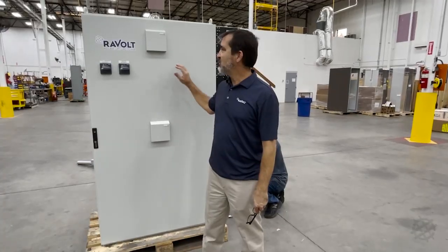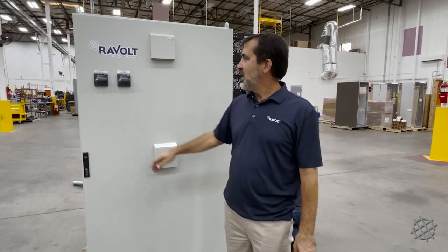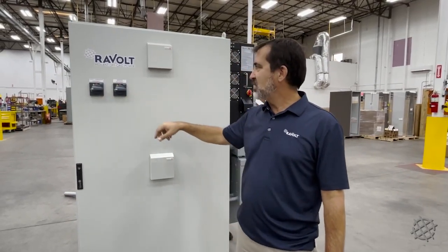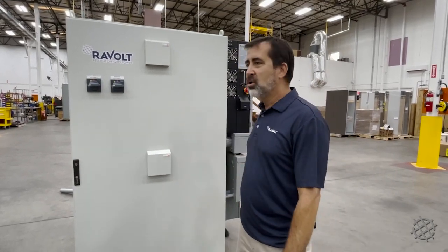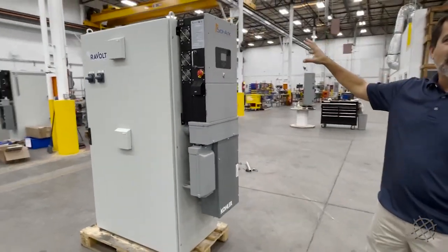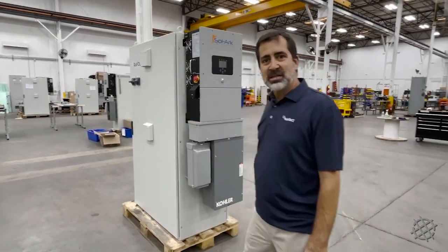We're standing right here in our manufacturing plant in Georgia looking at a Ravolt unit. This is our Level 1 unit. As you can see, it's got disconnects on the outside here to shut off both the utility and/or generator input, and to shut off the inverter output. From this unit you can power your whole load, whether it's your house or your house and barns and other things. We've got our solar inverters here that gather the solar energy and use it to charge the batteries housed inside a climate-controlled container.